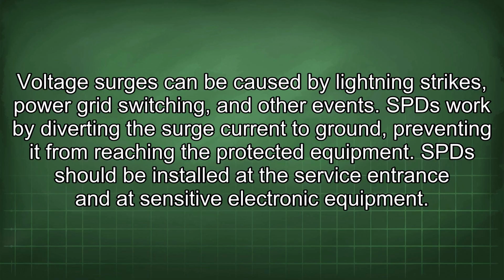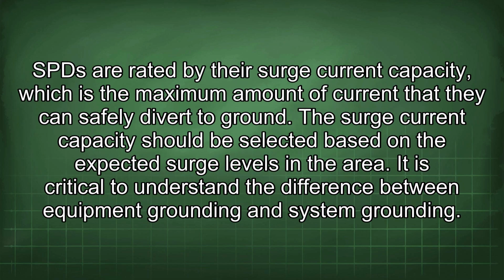SPDs should be installed at the service entrance and at sensitive electronic equipment. SPDs are rated by their surge current capacity, which is the maximum amount of current that they can safely divert to ground. The surge current capacity should be selected based on the expected surge levels in the area.